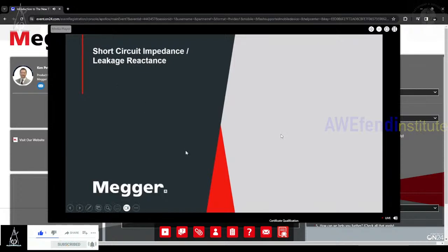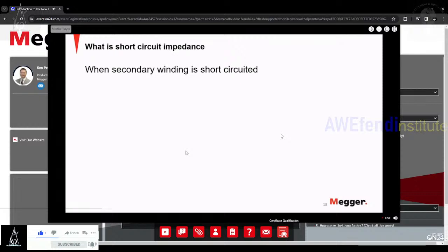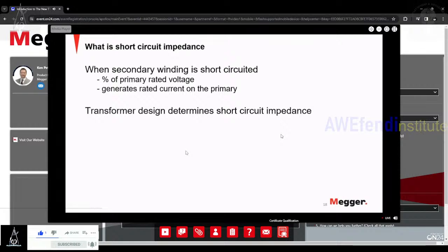The last testing feature that we've included in the TTRU1 is the ability to measure short circuit impedance, otherwise known as leakage reactance. What is short circuit impedance? This is a value that's stamped on nearly every transformer nameplate, as required by the standards. What it represents is a percent of primary rated voltage that would generate rated current. So if you see a Z% of 5 and the transformer is a 100 kV transformer, that means with 5% of the rated voltage, you will get 100% of primary current. And this is typically used to influence the network that the transformer is connected to.